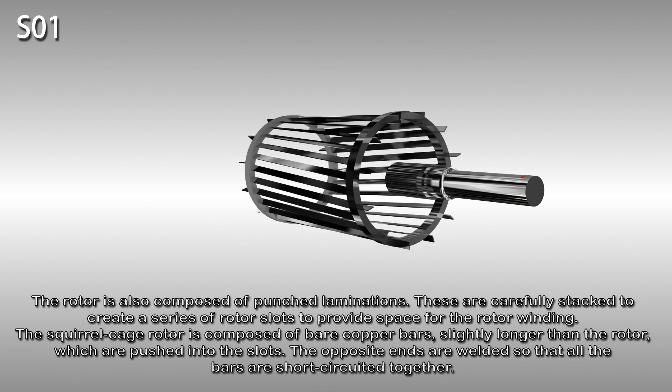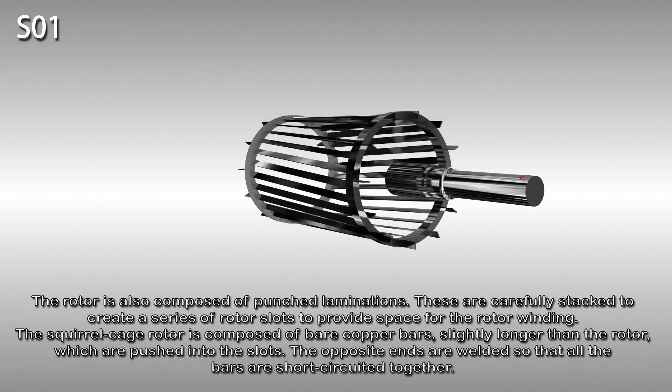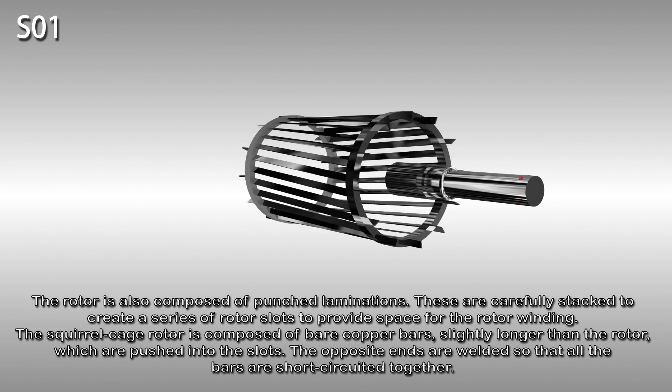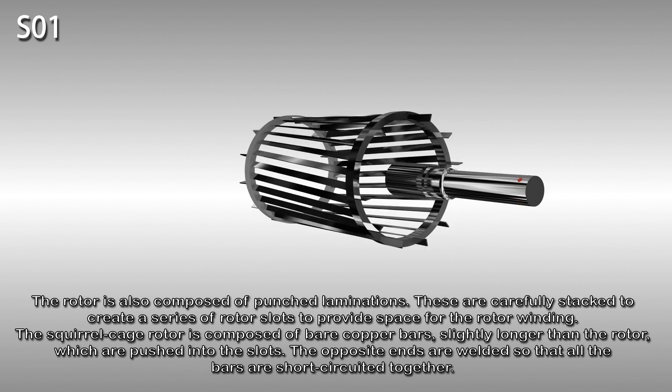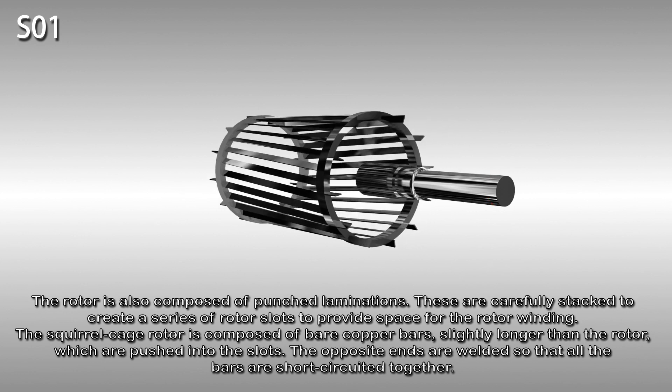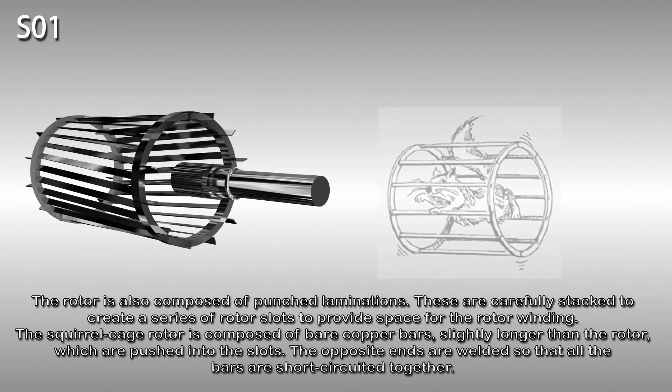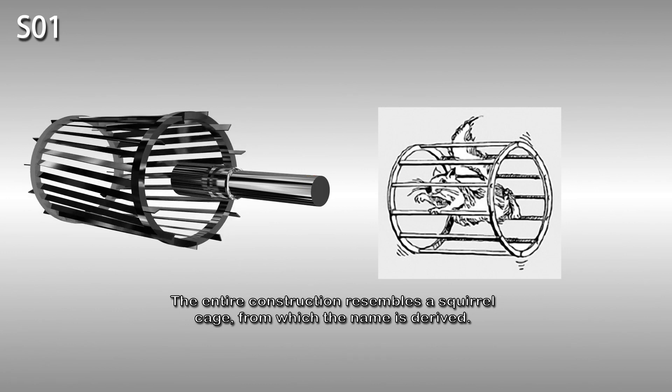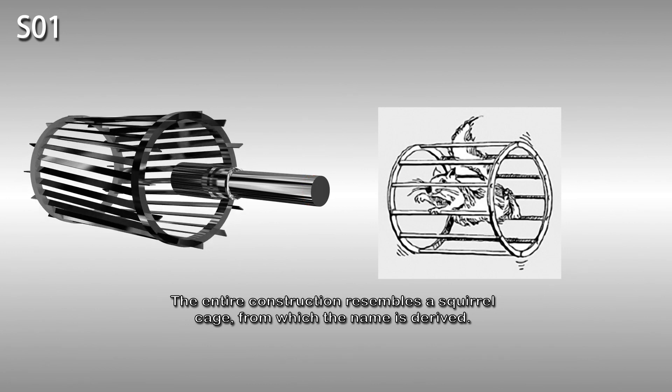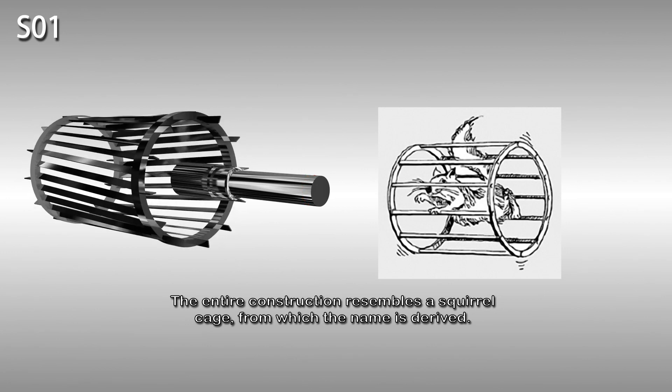The squirrel cage rotor is composed of bare copper bars, slightly longer than the rotor, which are pushed into the slots. The opposite ends are welded so that all the bars are short-circuited together. The entire construction resembles a squirrel cage from which the name is derived.